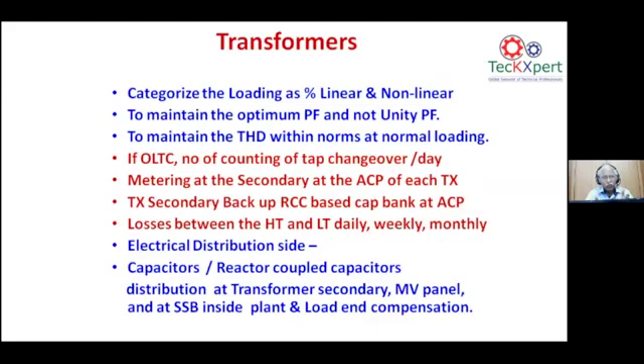Optimum power factor means every week you keep it at 0.96, 0.98, next week 0.99. At which power factor the capacitors are not burdening you, and at the same time your voltages and your electrical distribution are stable. This is where the optimum power factor is achieved. Then on the THD, power quality, what THD are we maintaining within the norms at the normal load? If you are using an OLTC in the industry, the number of tap changes the OLTC is operating per day will decide the functioning of the OLTC, and you can fine tune the OLTC band in such a way that the tap changeovers are less. At the same time, you are stabilizing the voltage downstream for the industry.